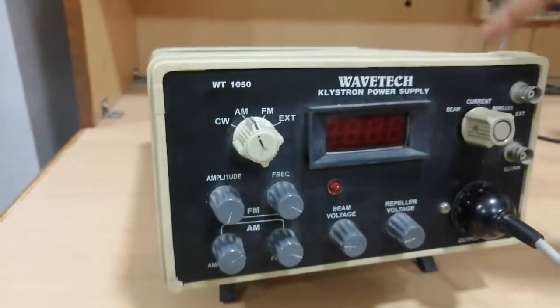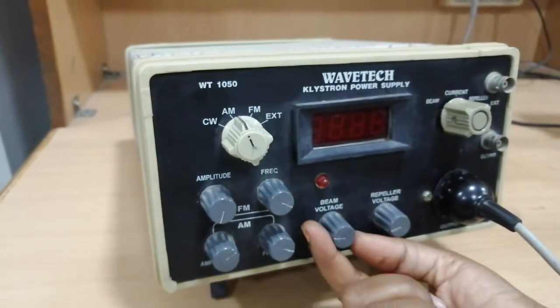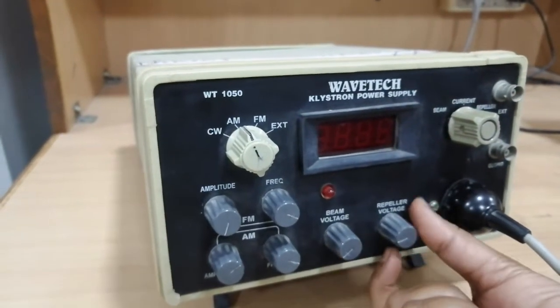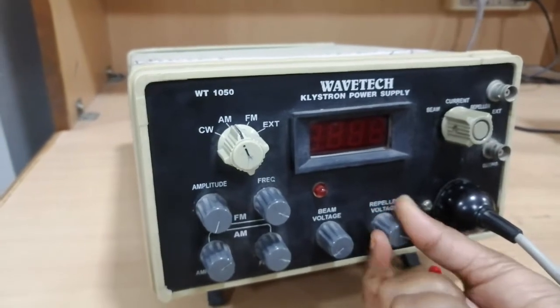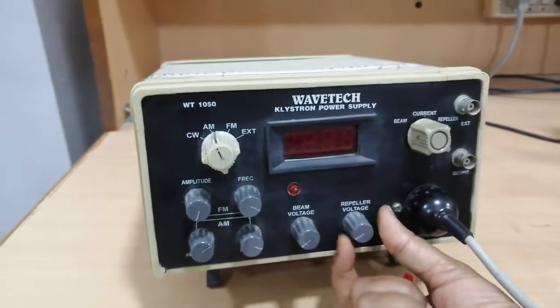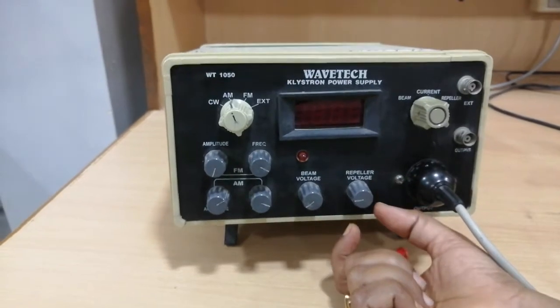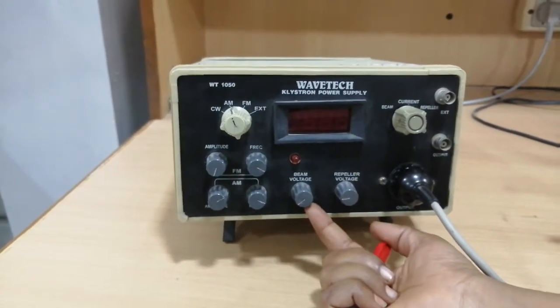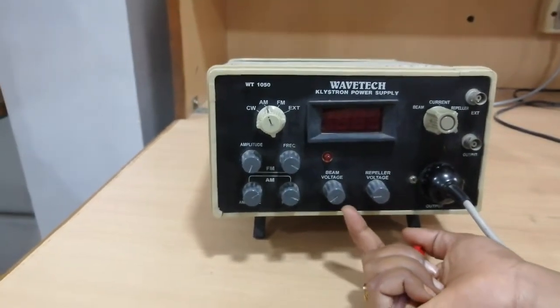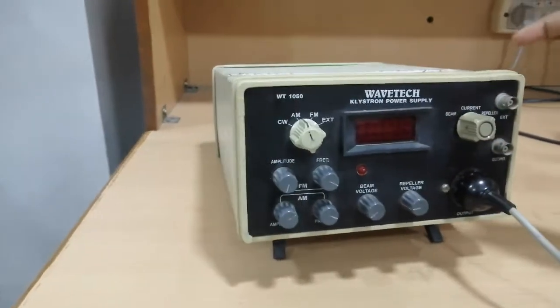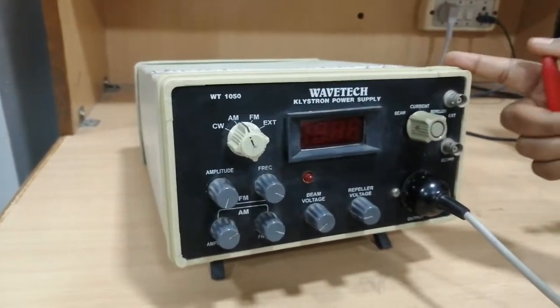In order to operate this klystron power supply, my beam voltage must be in minimum position and my repeller voltage must be in maximum position. So repeller must be varied from maximum to minimum and beam voltage must be varied from minimum to maximum. So this is about klystron power supply.